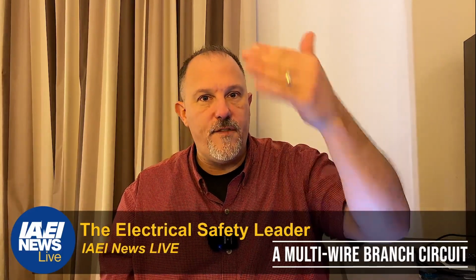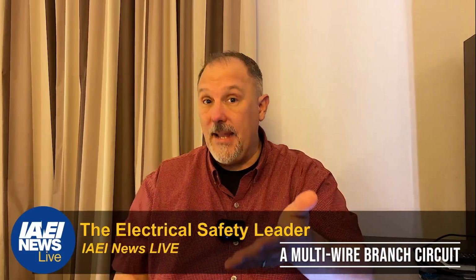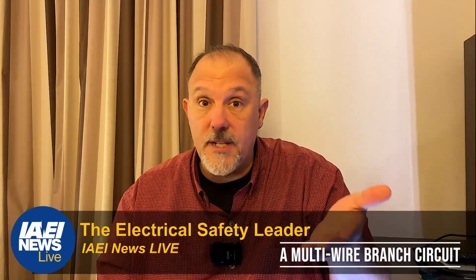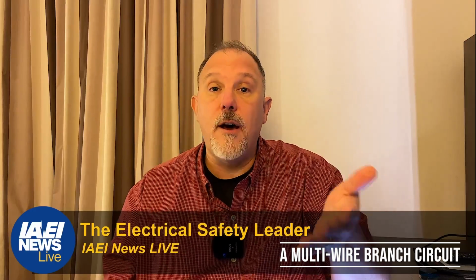So if two or more branch circuits are supplying devices or equipment on the same yoke, think about how we get that done. We take a duplex receptacle and we break the tabs, separating the top receptacle from the bottom receptacle. Now those are both independent receptacles. What might we do? We have two breakers, two branch circuits, one feeding the top, one feeding the bottom. Maybe the bottom is a switched receptacle, and maybe the top is not a switched receptacle, or vice versa.